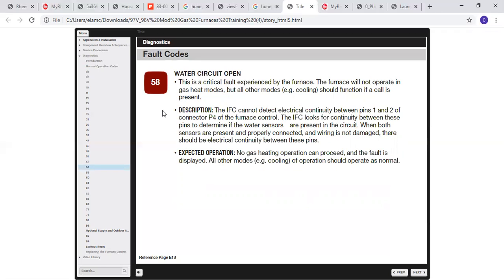58. This describes the water circuits. In this case here, it's a water circuit open. This is a critical fault. The furnace will not operate in heat modes, but it will operate in cooling. So if you have a water circuit that's open, you have 3 points of contact for your water circuits. You have your 2 switches, and you also have the IFC control board. Best thing to do on those, because it's determining that they're open, take all connections loose, inspect your connections, check for corrosion or damage on the 2-pin connectors. If everything looks good, there's no water in there or anything else, go ahead and snap those all back in and see if the fault disappears.